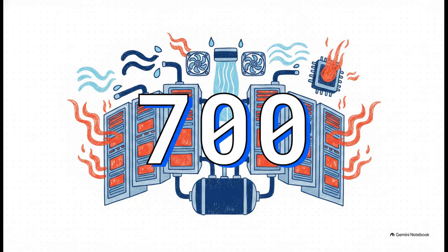Let's start with a number: 700 watts. That's how much power a single, recent, high-end GPU can consume all by itself. Just a few years ago, we were worried about CPUs that generated maybe 200 or 300 watts. Now, with the explosion of AI and advanced processing, we're looking at silicon that runs incredibly hot. Just imagine a standard server rack packed with these things. A modern system with just 2 CPUs and 8 of these high-performance GPUs requires about 7 kilowatts of cooling capacity. That's a staggering amount of thermal energy.